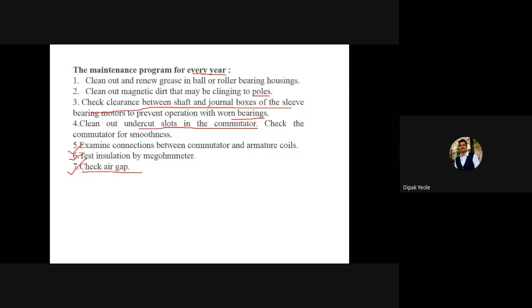So this is a very important concept. We have to check the air gap. If the air gap increases or decreases, there can be an adverse effect on that particular induction motor or on any electrical equipment. So this is the maintenance program for every week, every 5 to 6 months, and every year.